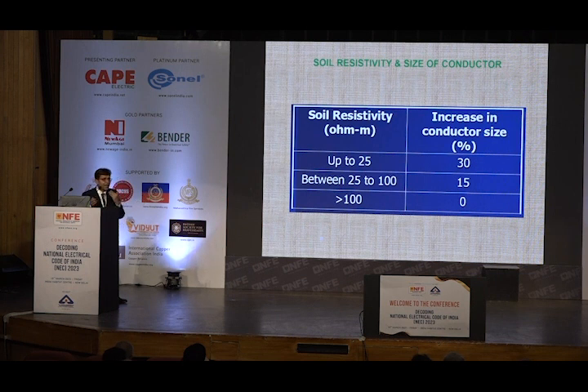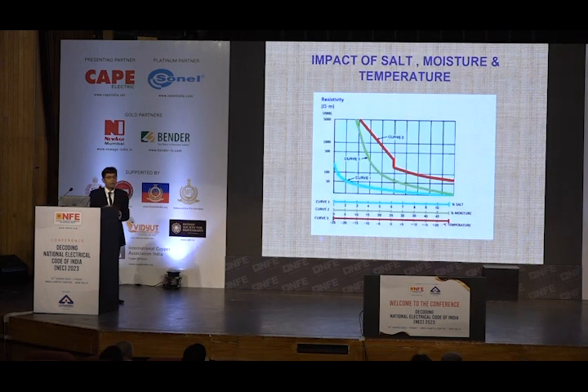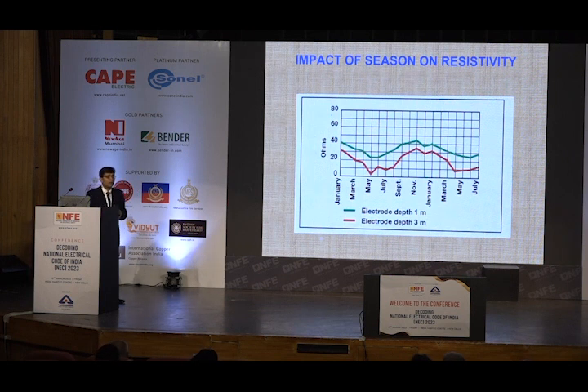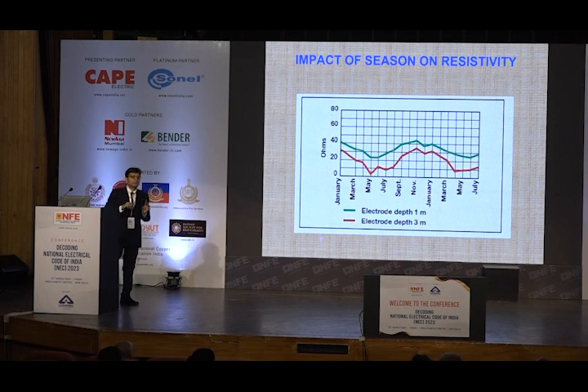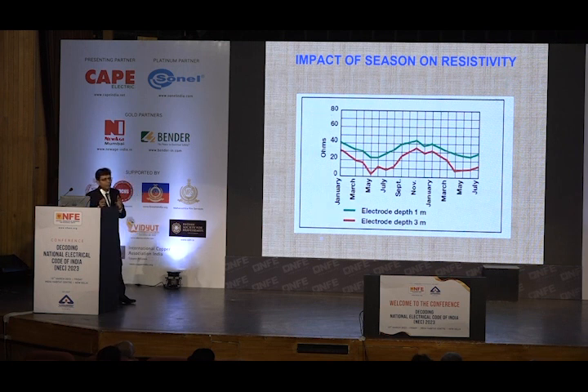Up to 25, that means it is highly corrosive, you have to take a 30% safety margin. Up to 100, 15%, and more than 100, no need to take any safety margin. This picture gives the impacts of salt, moisture, and temperature. Soil resistivity is also weather dependent, and depends on the particular day of the particular month you are measuring that resistivity. That will definitely vary, and you have to use that measurement value wisely for designing your system. Otherwise, you will end up with over design or sometimes under design. Be careful.